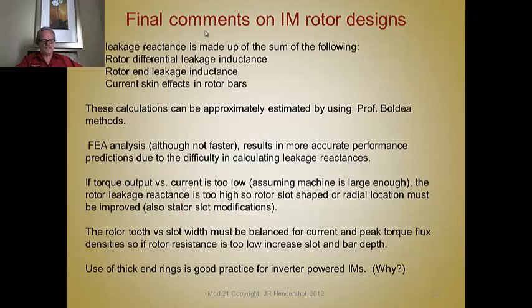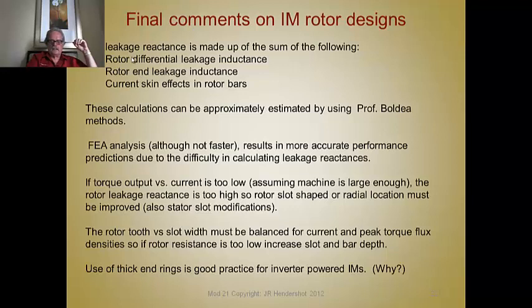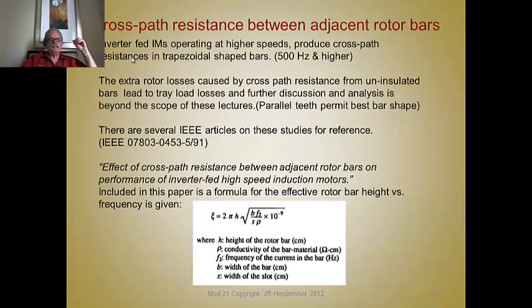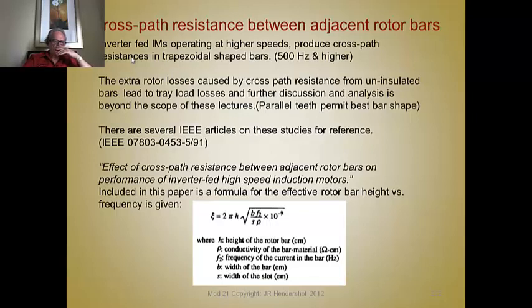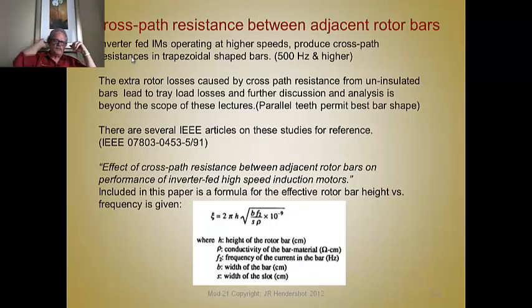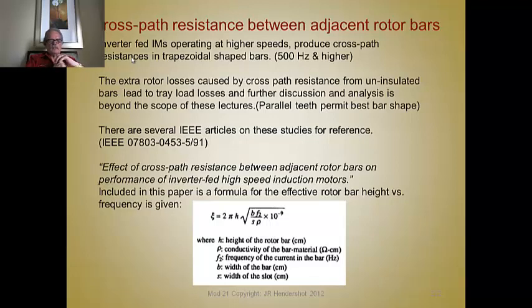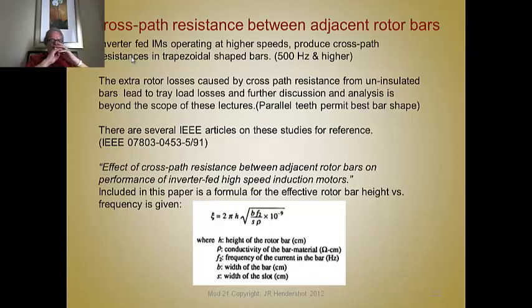If the rotor resistance is too low, increase the slot and bar width. Using thick end rings is good practice for inverter-powered induction motors. There is a phenomenon that exists in rotors at higher frequencies: a cross-path resistance that develops in inverter-fed machines operating at higher speeds in trapezoidal-shaped bars — which are the bars we want to use anyway. This is probably a problem at 500 Hz and higher. These extra rotor losses are caused by cross-path resistances because the bars are uninsulated from the core — and there's really no way to insulate them — leading to stray load losses. Further discussion of this is beyond the scope of these lectures.